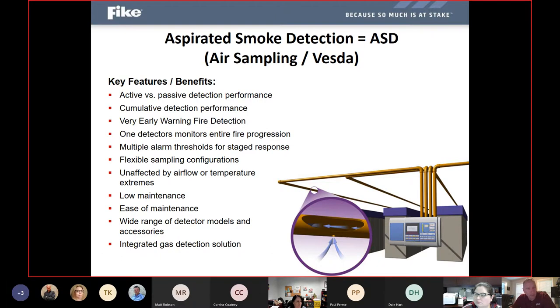On the other spectrum of the flame detection, again, is smoke detection. One of our very early warning smoke detection systems, which you may already be familiar with, is VESDA. Just a real quick overview: instead of having a regular smoke detector up on the ceiling like you would at your home in your bedroom and throughout your hallways, this is more of an active smoke detection system, because we've got a main unit hanging on the wall somewhere that's got a small aspirating fan inside of it. And we send pipe networks out to the areas. Those piping networks are drilled with engineered size holes so that we can ensure and control how much air we're pulling from the entire piping network.